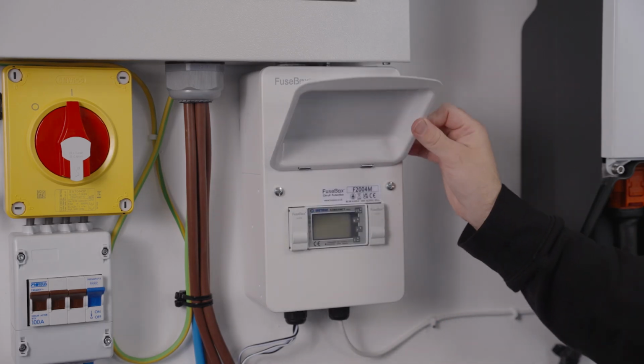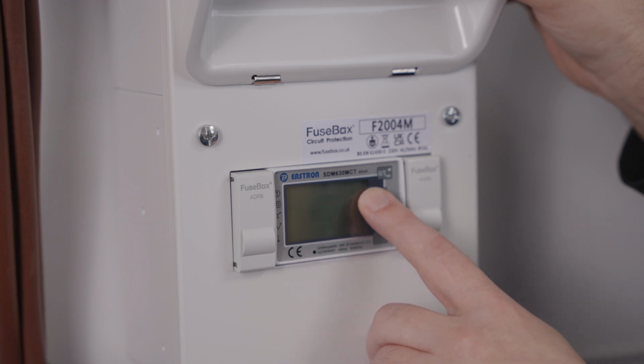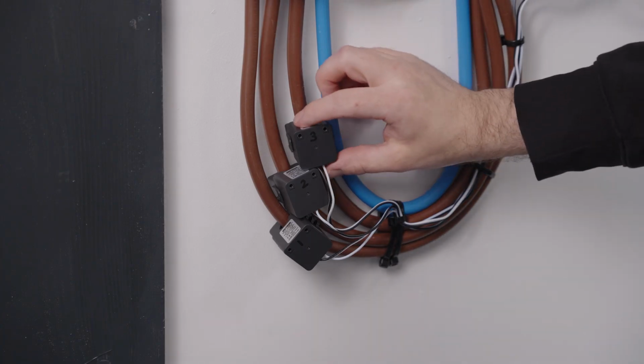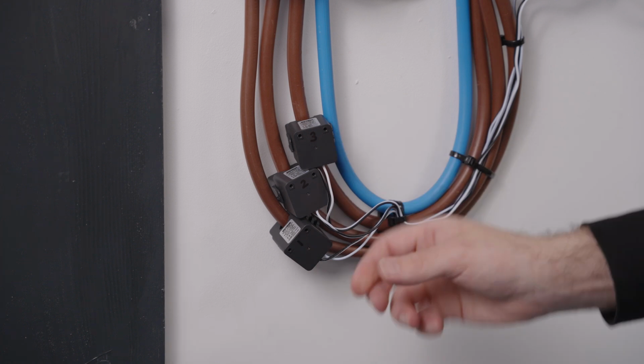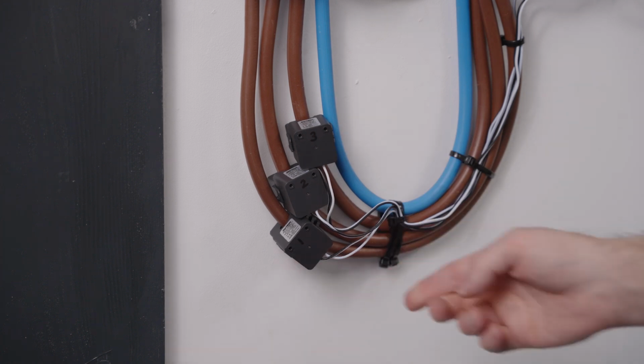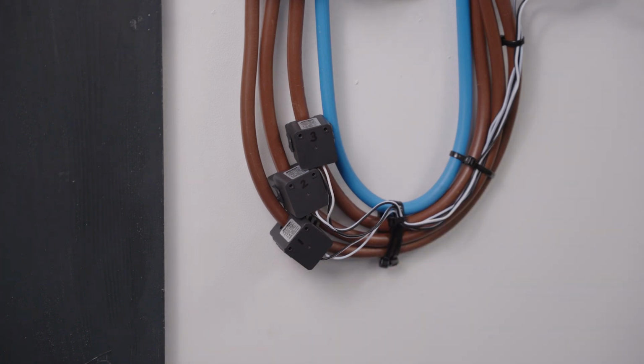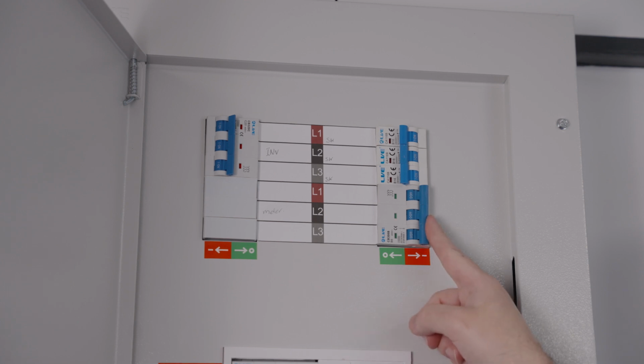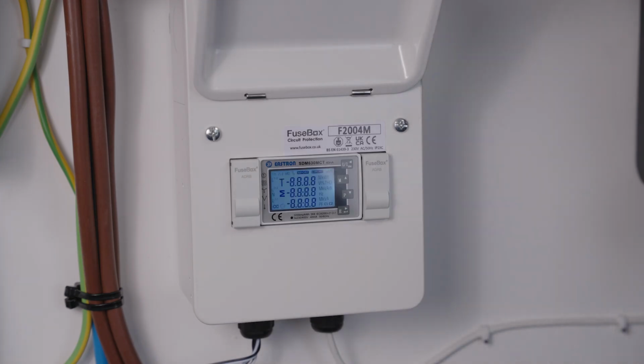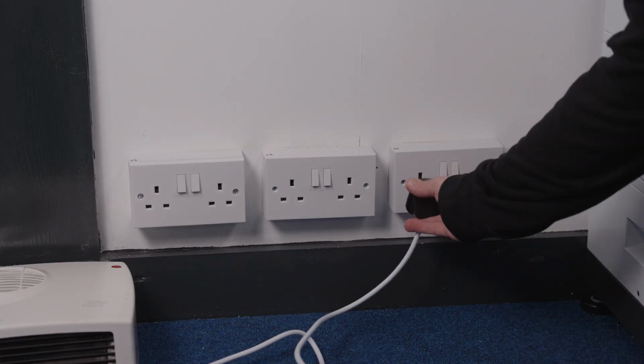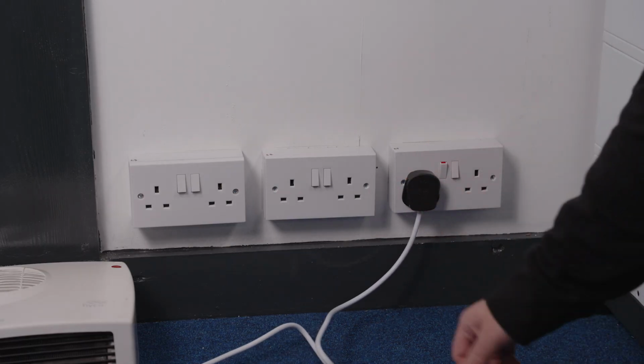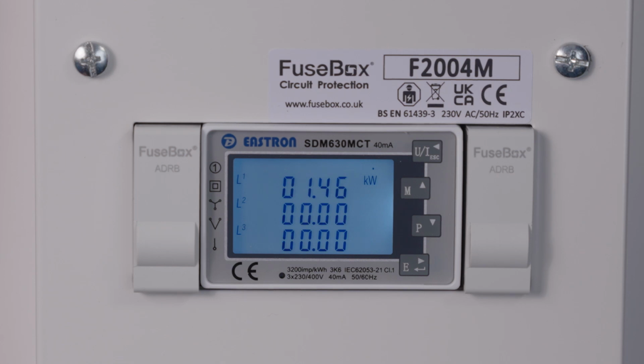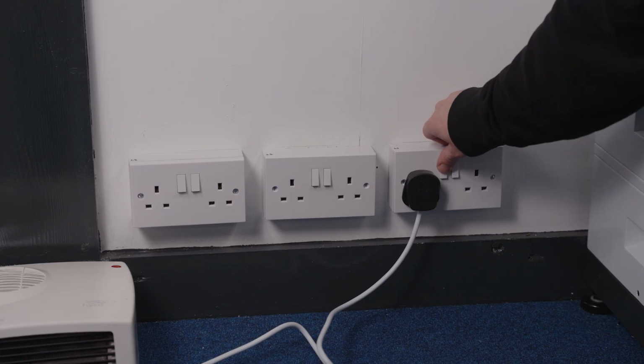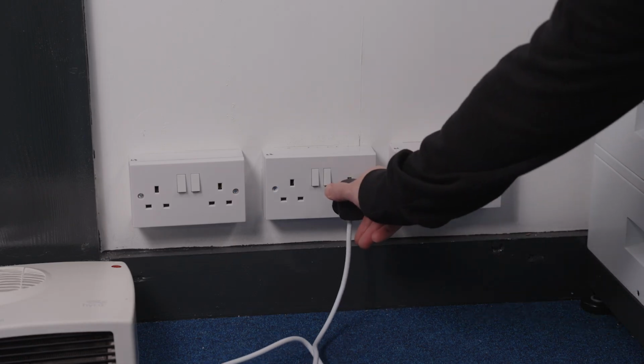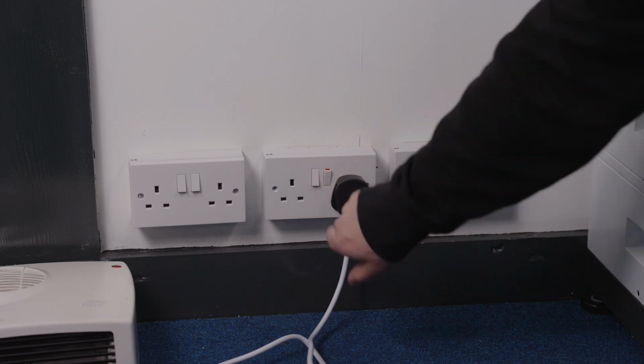Ensure that you have the correct meter model. If using the CT meter not in line, install the 3 correct direction CT clamps like this. Turn the meter on and ensure the CT clamps are monitoring the correct phases by performing a load test. Do this by using a known load against each individual phase and checking the reading on the meter. Checking that it is powered from the correct phases is important to ensure correct system performance.